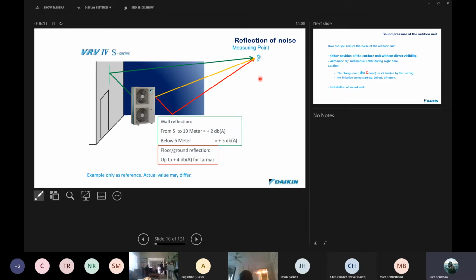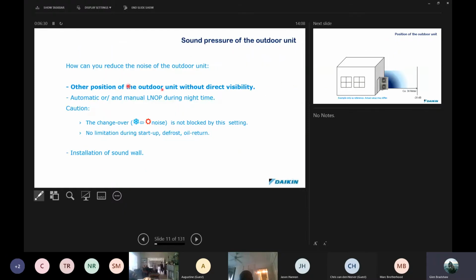Okay, so sound is very important to consider, and we've had many cases where units installed in areas have become problematic for this because consideration was never taken in the placement. So there are many ways that we can solve this, and some of the ways that Daikin have got. How can we reduce the noise of the outdoor unit? Well, we can find another position for the outdoor unit without direct visibility. When you're not in direct line of sight of sound, that does tend to take out quite a bit of the perception of noise.